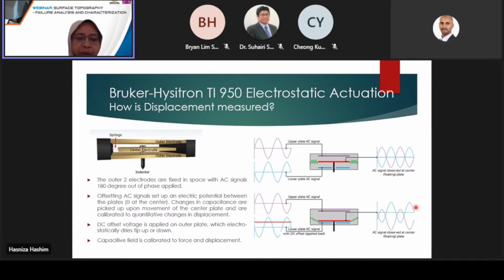Now, let's look at how the force is actually applied and how displacement is measured. In our system, the probe is installed into the floating metal plate of a 3-plate capacitive transducer. The displacement is measured by running two AC signals, 180 degrees out of phase with each other, to the top and bottom plates of the 3-plate capacitive sensor. The AC signals are picked up by the center plate, and the sum of the signals corresponds to a measured displacement. To apply load, a DC offset is applied to the lower plate of the transducer that electrostatically attracts the center plate downward.